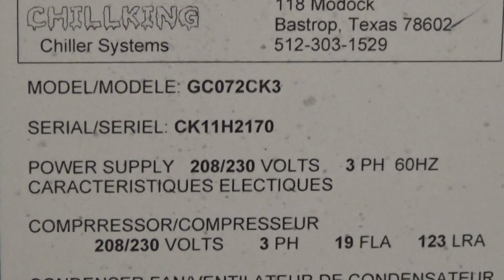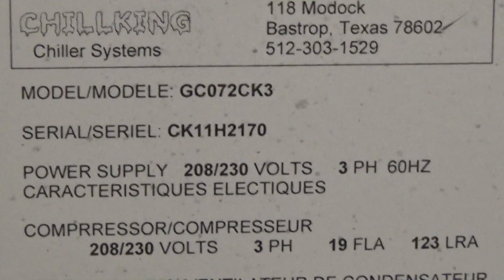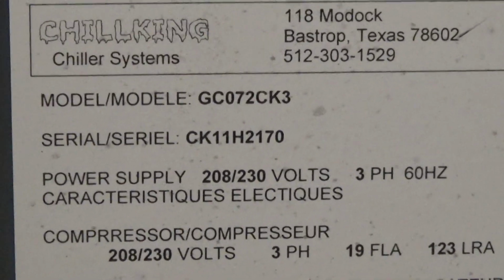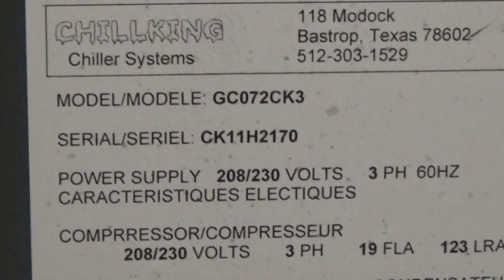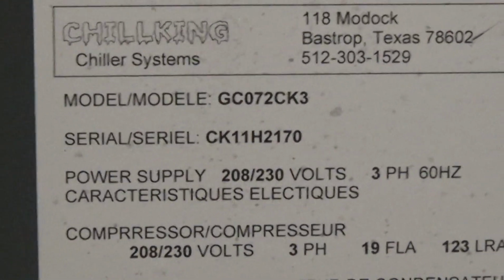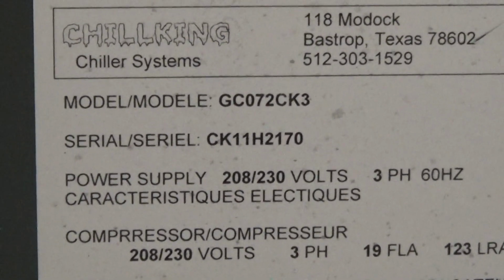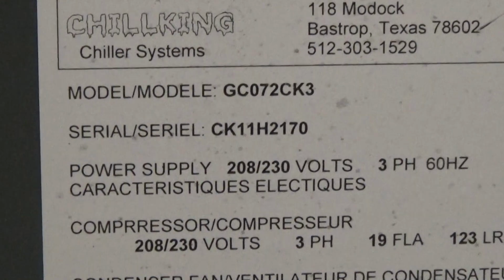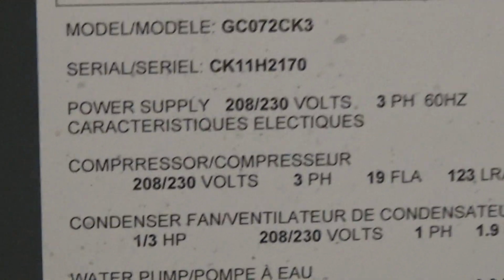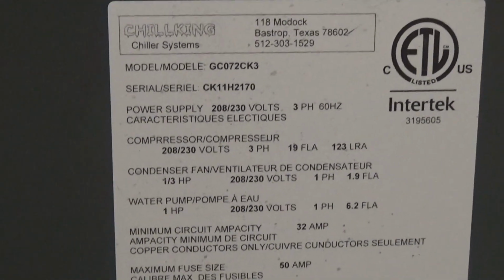This unit is model GC072CK3. The 72 stands for 72,000 BTUs at nominal temperatures. And it's a serial number CK11H2170. So that means it's made in 2011. It's 208, 230 volts, 3-phase.